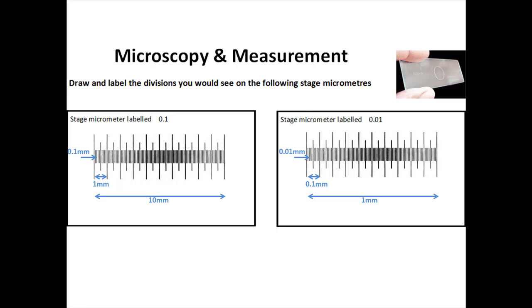Another simple way — even if the stage micrometer wasn't labeled — you can just hold it up to the light and have a look at it. If the whole thing looks roughly a centimeter, you know you've got a 0.1 micrometer: the whole thing is 10 millimeters, big line to big line is 1 millimeter, and the smallest unit is 0.1 millimeters. If the whole thing appears to be about a millimeter — so you can barely see it — then the whole thing is a millimeter, from one big line to the next big line will be 0.1 millimeters, and the tiniest units will be 0.01 millimeters.